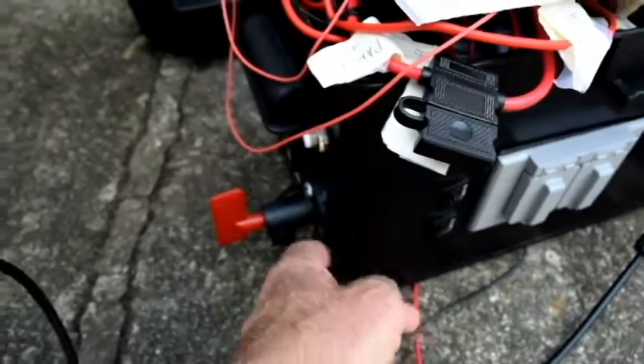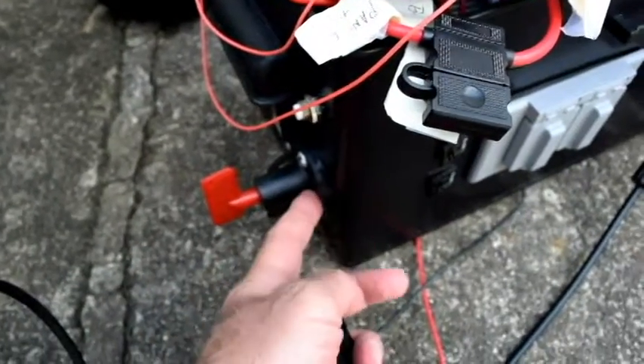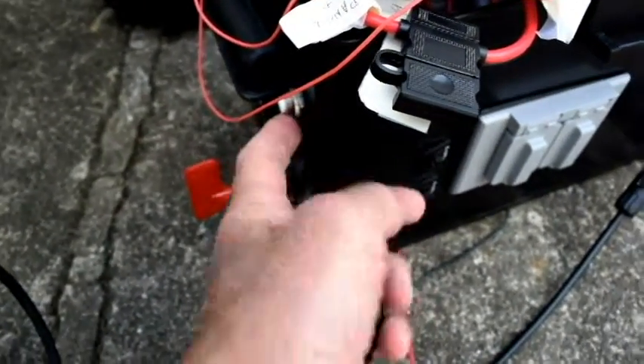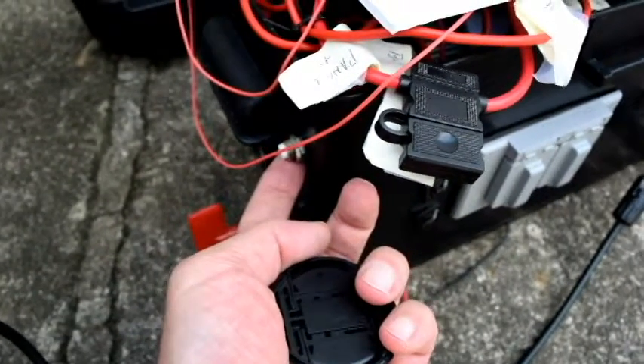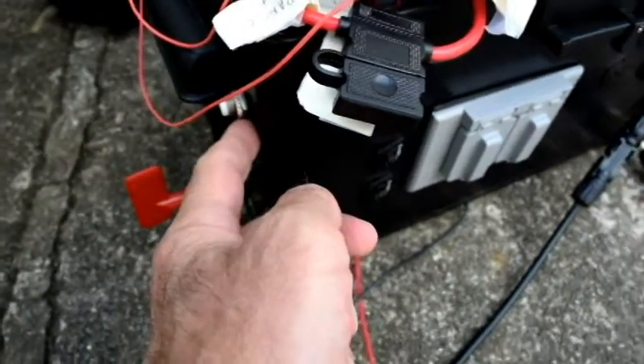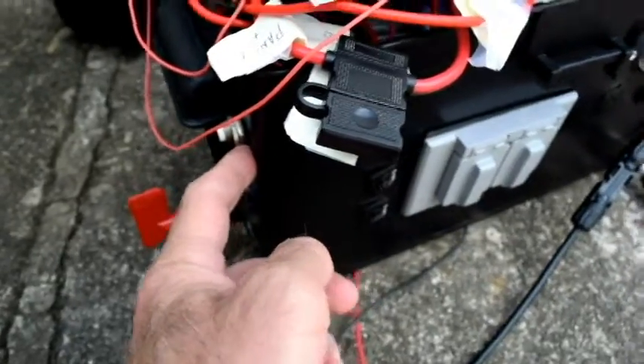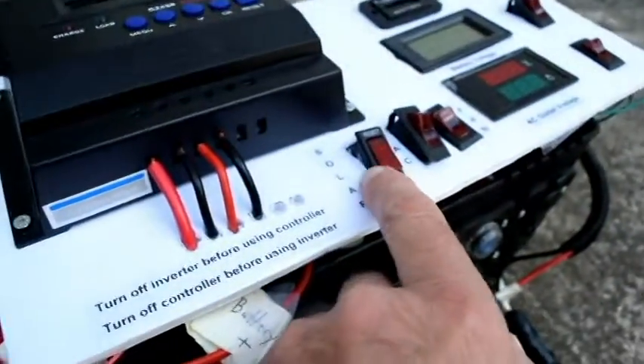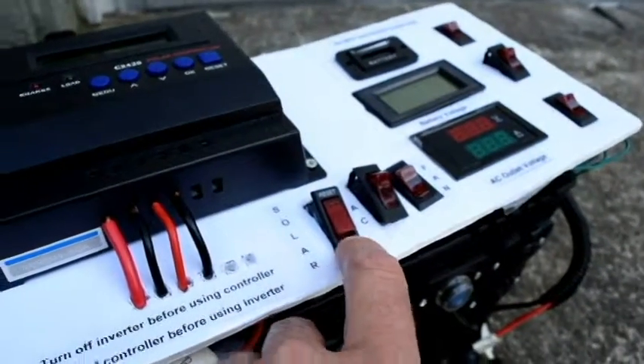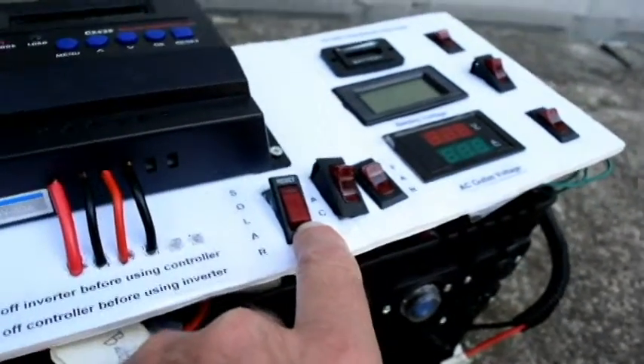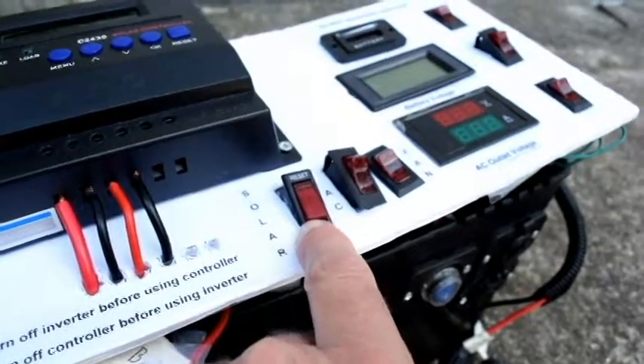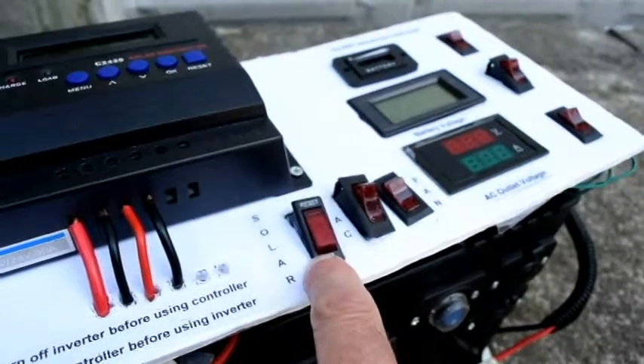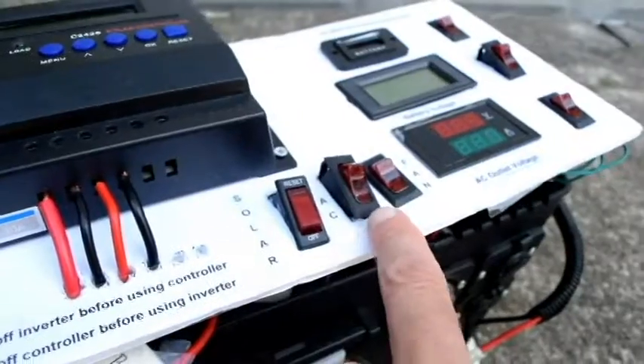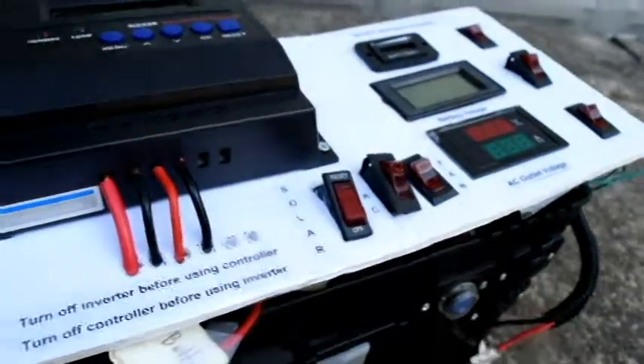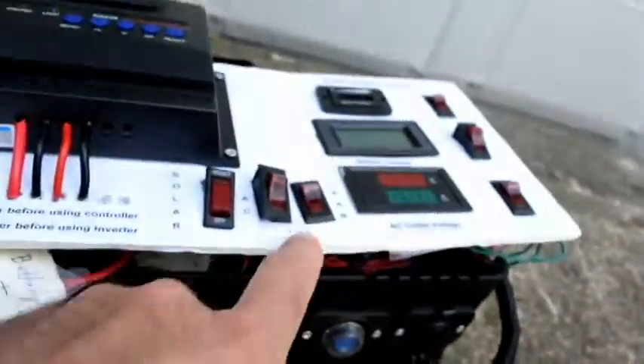So the positive wire comes into this quick disconnect. It splits up. This one goes directly to the inverter, through a 35 amp circuit breaker. This wire goes to the controller. This switch is actually a 30 amp circuit breaker. These two are switches. This one is to the inverter. The inverter already has this 35 amp circuit breaker.